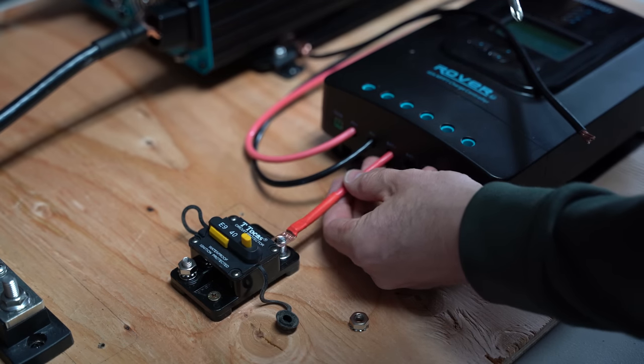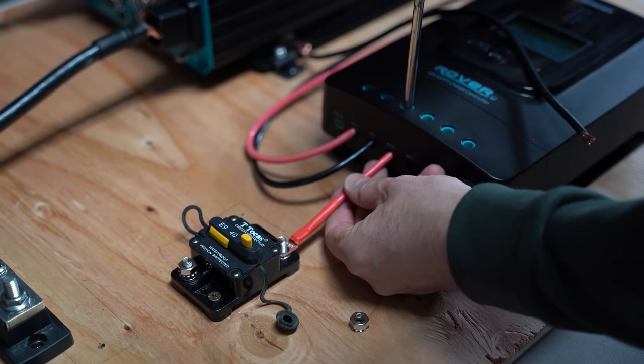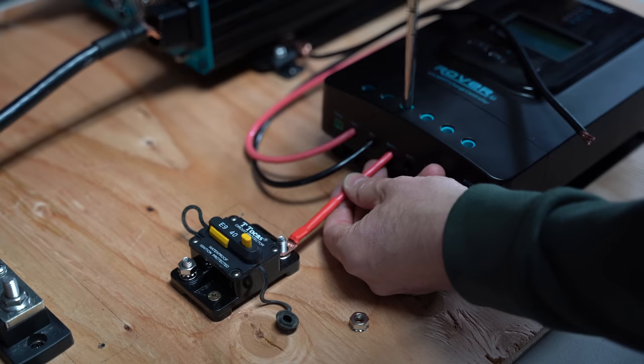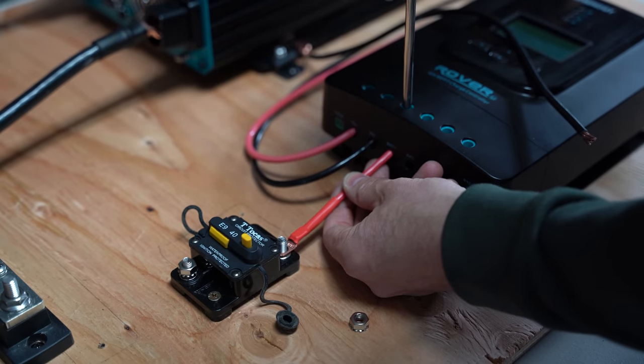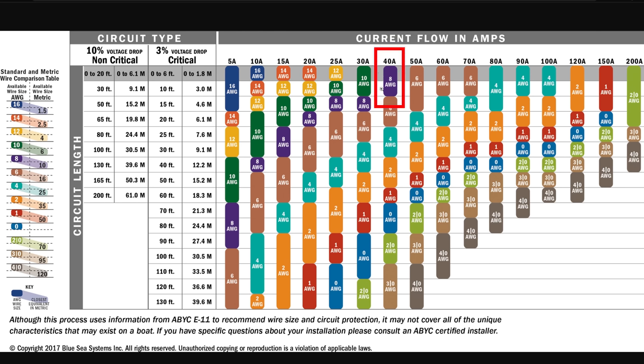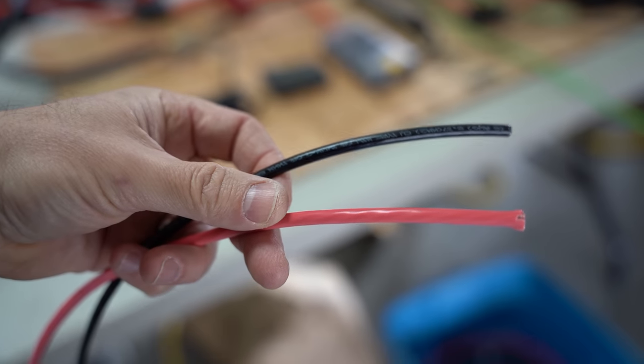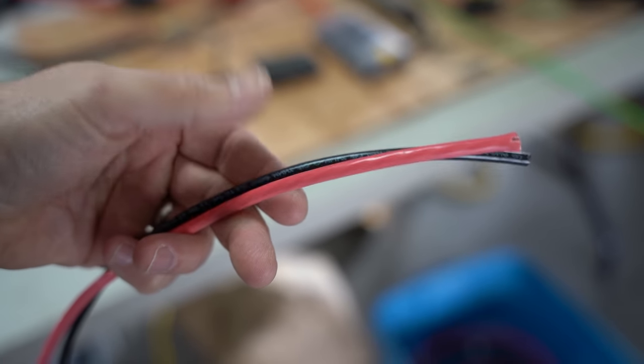But what size wiring and fuse should we add in here? Since this is a 40 amp charge controller, our wiring coming from the charge controller will need to be able to handle a maximum of 40 amps. According to our chart, 40 amps requires 8 gauge wiring. Again, I picked this up at Home Depot purchasing red and black 8 gauge wiring.